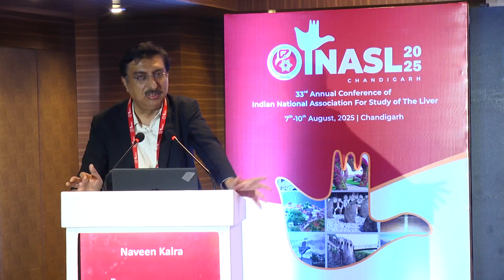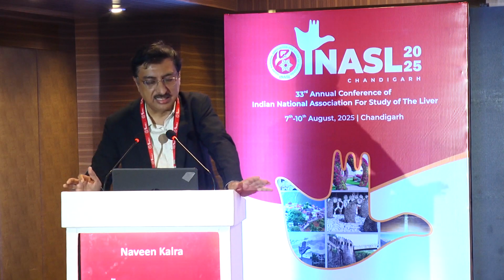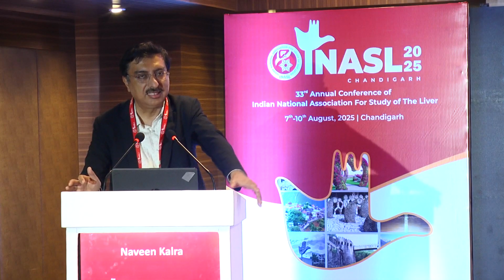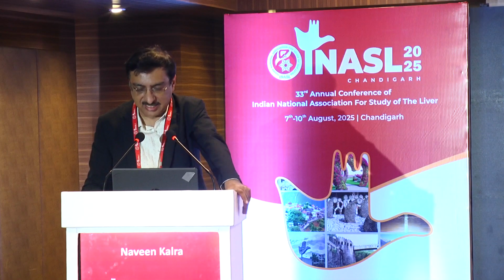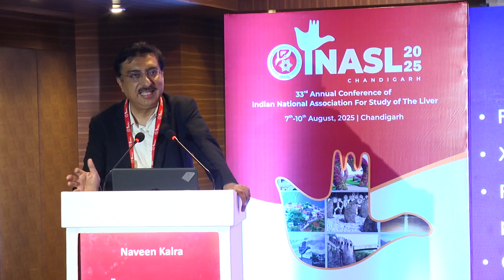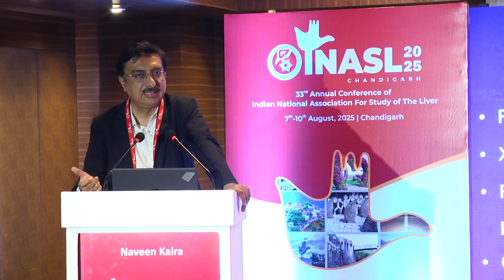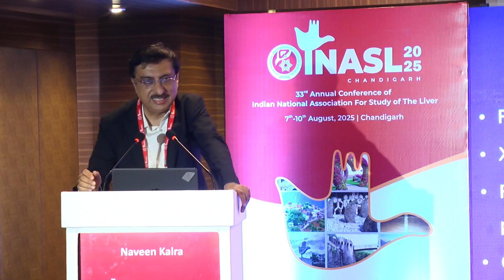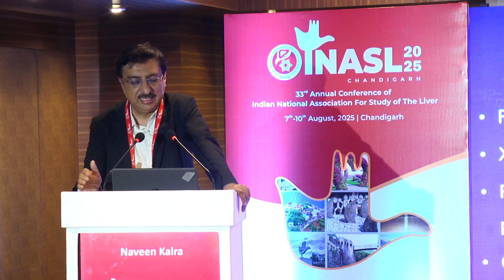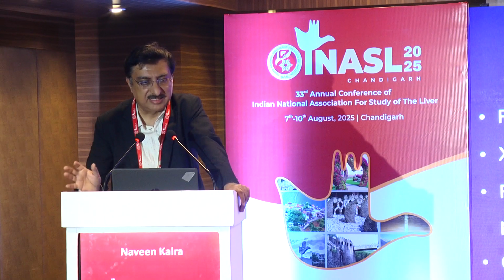And this blue box is the active driver, which lies outside the MR room, and the two are connected by a polyvinyl tubing. So where do you place the passive driver? You place it over the abdomen, and the points which help you to place it are the xiphoid and the mid clavicular line, and where they intersect, that is where you should place the passive driver.